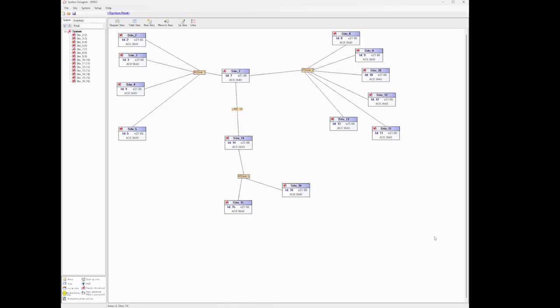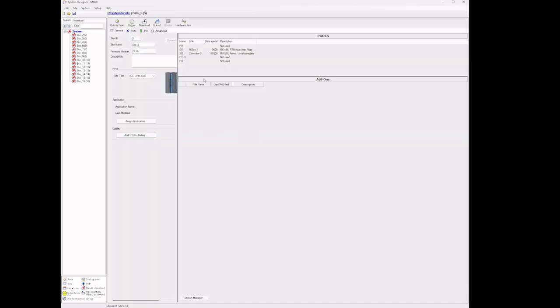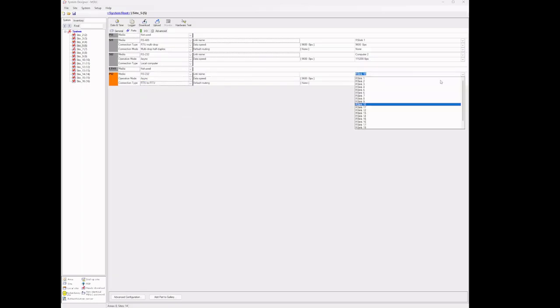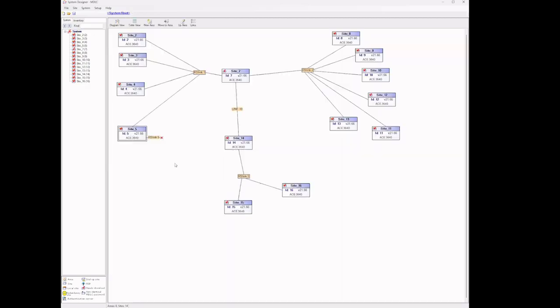Now it's important that when we configure RTUs in a system like this, we don't include any unused links. So for example, in this computer, if plugin 2 was used as an RTU to RTU, let's say an RS-232 port, and it had used RS-Link 9, it's important that while RS-Link 9 is not being used in the network, ideally it shouldn't be configured in the RTU, and that goes for any of the RTUs in the system.